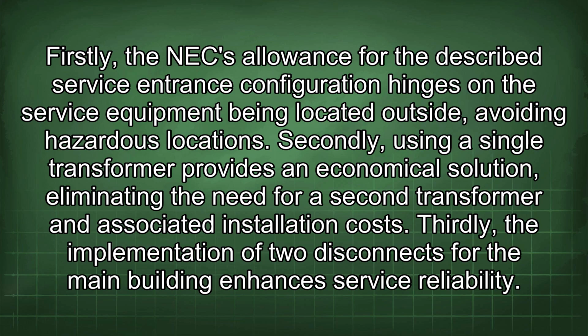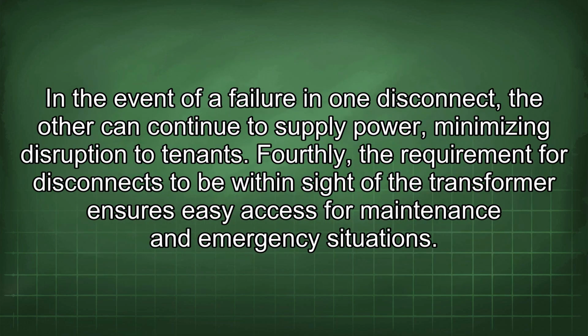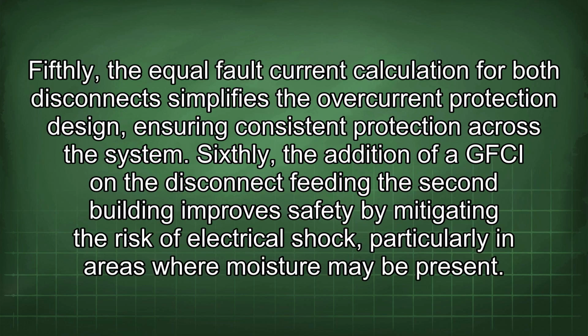Secondly, using a single transformer provides an economical solution, eliminating the need for a second transformer and associated installation costs. Thirdly, the implementation of two disconnects for the main building enhances service reliability. In the event of a failure in one disconnect, the other can continue to supply power, minimizing disruption to tenants. Fourthly, the requirement for disconnects to be within sight of the transformer ensures easy access for maintenance and emergency situations. Fifthly, the equal fault current calculation for both disconnects simplifies the overcurrent protection design, ensuring consistent protection across the system.